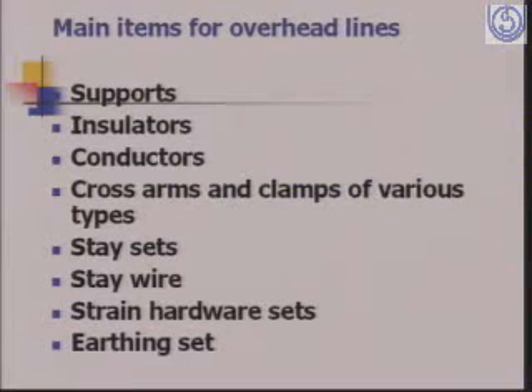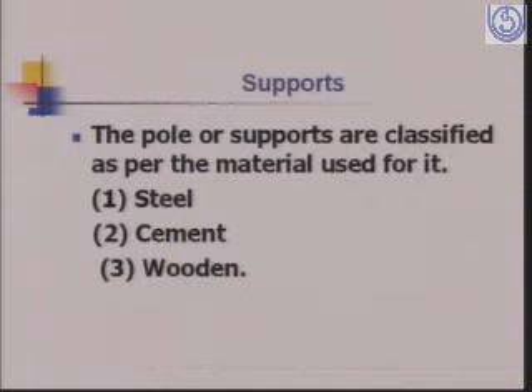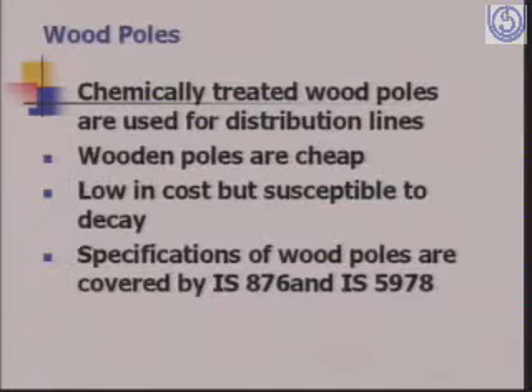The main items for overhead lines are the supports, the insulators, the conductors, the cross arms and clamps of various types, the stay sets, the stay wire, the strain hardware sets, and the earthing sets. For example, we'll start with the supports. The pole or supports are classified as per the material used for the support. They can be made of steel, cement or wooden. We'll go first to the wooden poles.